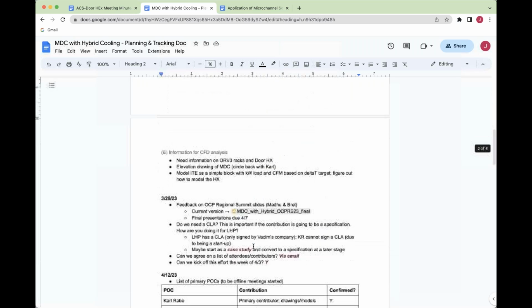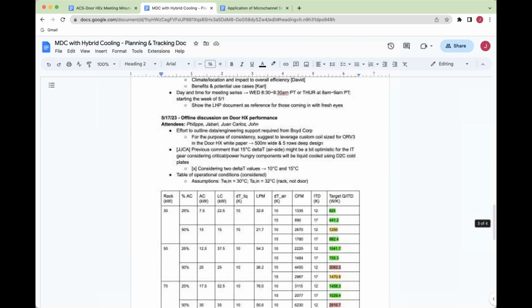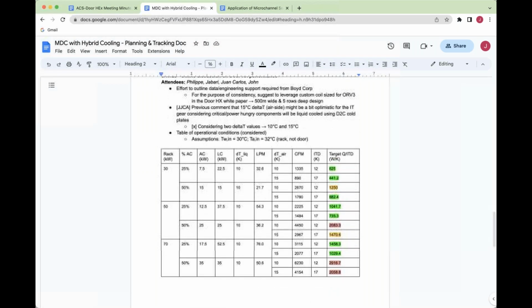In the offline discussion, we put together a table looking at the three different power levels, how much is air cooled versus liquid cooled, different air-side delta T's, and the corresponding required raw performance of the coil. We define this as cooling capacity over initial temperature difference, so it's watts per Kelvin.